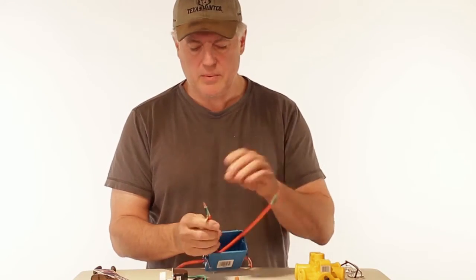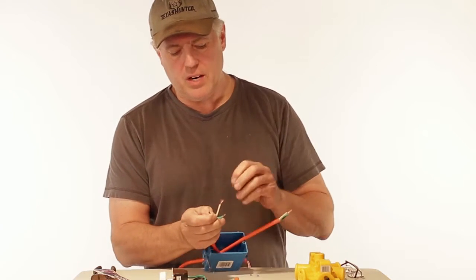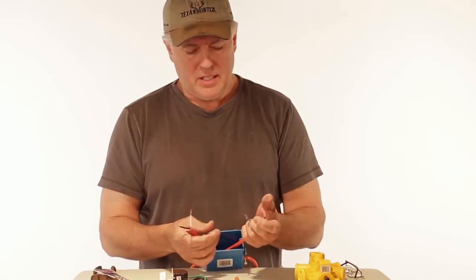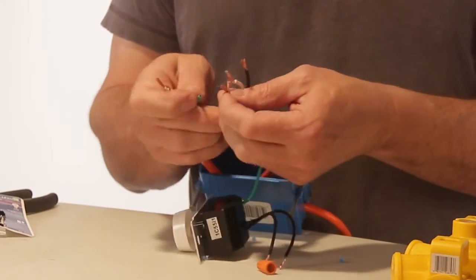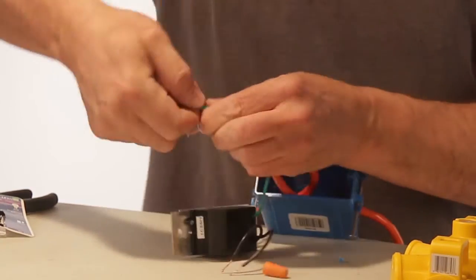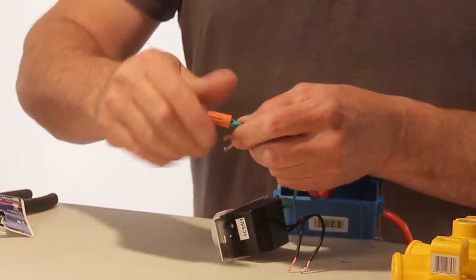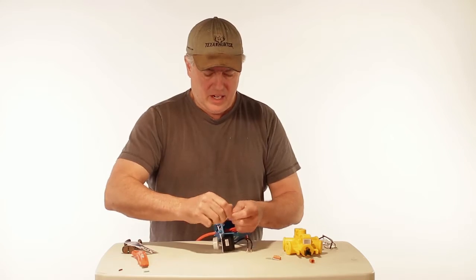We have both of our cables out here. Now it's time to wire them together to the rheostat. First thing we're going to do is wire all the greens together — that way we know the green will not be used later on any of this. Grab all your greens, including the rheostat green, put them together and give it a little twist. I've got these little orange wire nuts — what they do is cover the wire and hold them together — so twist that on there as well.